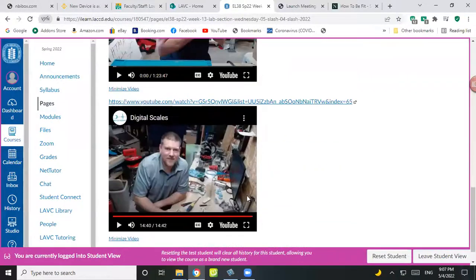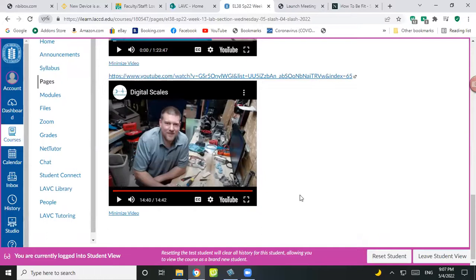Okay, so I'm not sure that he's going to be able to put this back together. I have not seen the video after he put this together. So I don't know what troubleshooting solution he found for the problem. Normally, when you turn on these scales, especially these models, you get an error code. The error code is in the operation manual. I remember this manufacturer has a troubleshooting chart in the back of the user manual. It tells you what the problem is, so you can follow the troubleshooting guides. I don't think he's looked at that troubleshooting guide and chart yet.